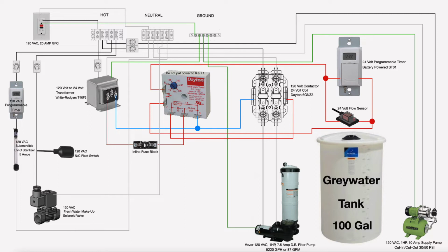And the time delay relay gets its 24 volt power supply from this step down transformer. You can see it's 120 volts coming in on the primary wires of the transformer, and then on the secondary side, or the output side of the transformer, it's 24 volts. And there's an inline fuse here.